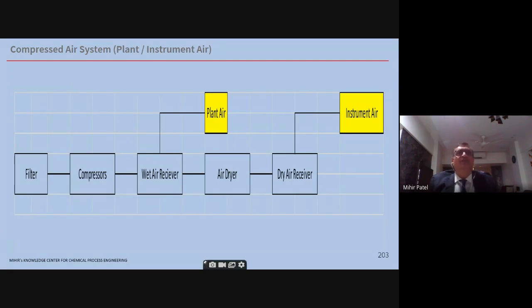You can have an oil filter at the outlet and make sure the oil specification is specified and the oil filter is procured for that oil specification only. Wet air receiver is planned. It's about 3 to 5 minutes storage. Air dryer is there. Air dryer is of many types again.